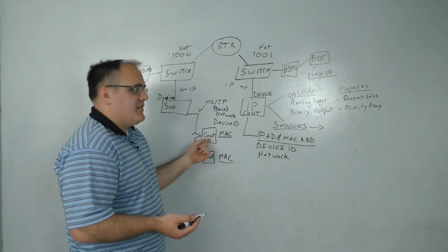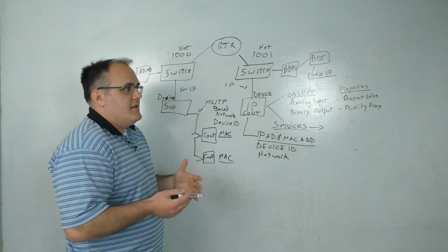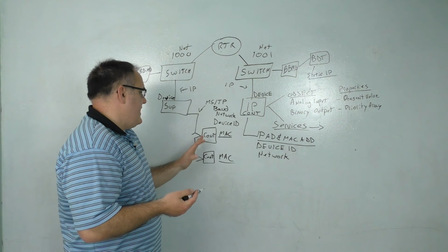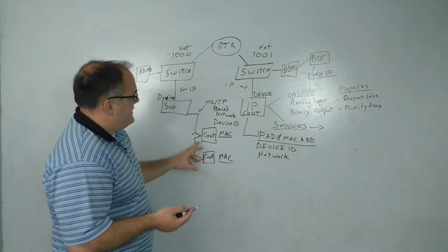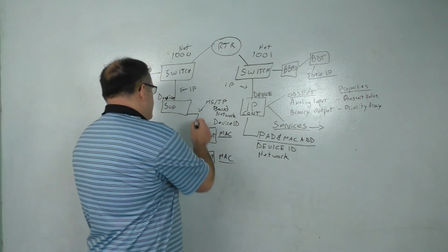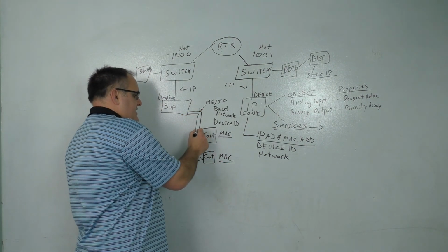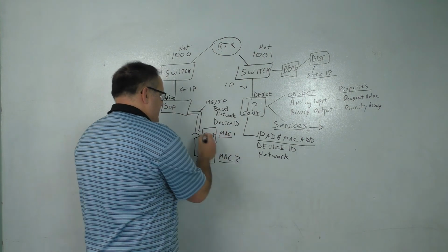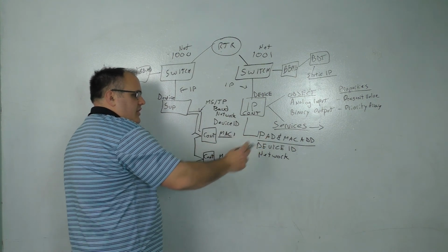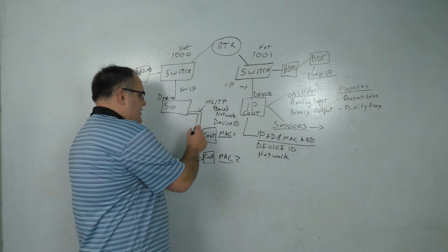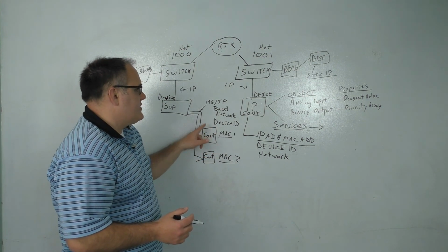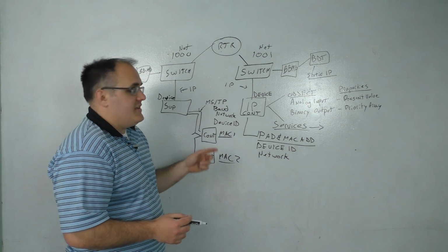Because if this thing's communicating the token at 36K baud and this thing's at 72K baud, then what's going on is that these two controllers are going to have data collisions. So basically the token goes from the supervisory device and it travels down in order. So if this is MAC 1, this is MAC 2. If there's any application service requests that have to go across, which we'll cover in just a second, they're attached to the token.